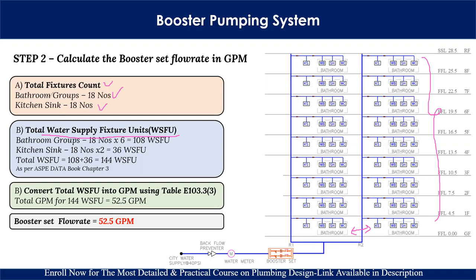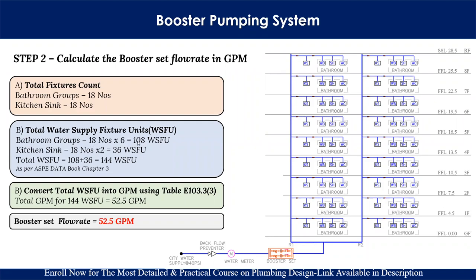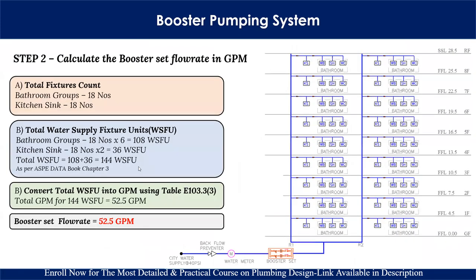We need the WSFU values for the bathroom group and kitchen sink, which we get by referencing the ASPE — American Society of Plumbing Engineers — standard. In the table, for a bathroom group with private occupancy, the WSFU value is 6. So: 18 × 6 = 108 WSFU for bathroom groups. For kitchen sink with private occupancy, the WSFU value is 2. So: 18 × 2 = 36 WSFU. Adding both: 108 + 36 = 144 WSFU for the complete building.